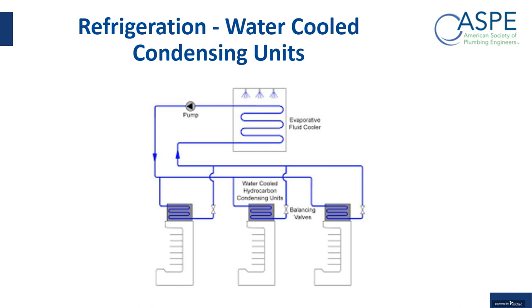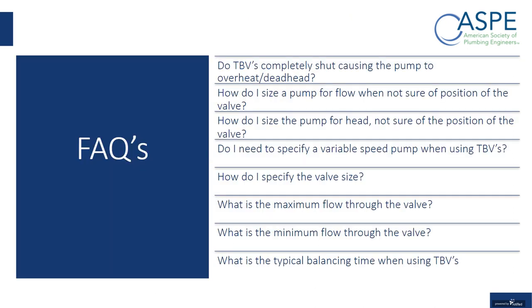So an example real quick could be in a grocery store, a refrigerated unit which has like 3 doors to it. And you have the person in the center who opens the door to buy some ice cream and they can't determine what ice cream they want. And they're leaving that door wide open and all the hot air is getting in there and warming up the whole system. So with thermostatic balancing valves in this location, this is going to keep on adjusting the flow to what it has to make sure it keeps the system cool. So this is another application for it.